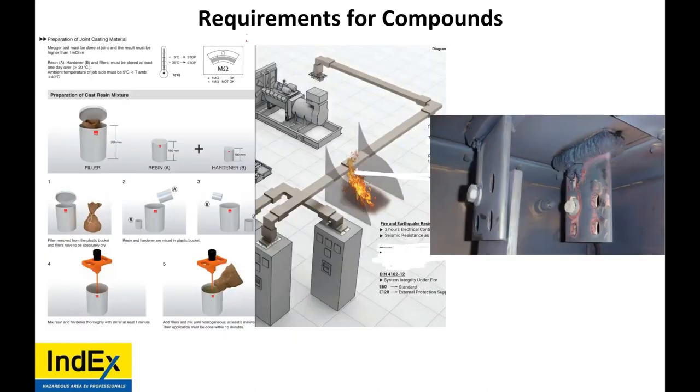So what are we looking at? Well, the reason manufacturers have these EXM busducts is that, instead of using cables, you can use something that is earthquake proof, fireproof, and can transition zones. It can go between a non-hazardous area, a zone 2, and a zone 1 all the way. So it can go from switchgear or a transformer all the way over to a motor or a compressor on a train, a big GE or BH compressor. It's waterproof, it's fireproof, and it's also rated for earthquakes. So they specifically tell you how to pour these joints.